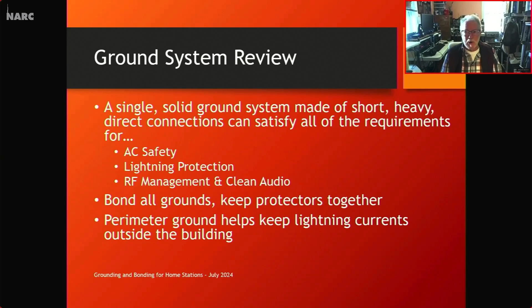You want to make sure you bond all these grounds and your protectors together so they fire at the same time, so everything goes up and down together and you don't get individual destructive transients. When you use a perimeter ground system, it helps keep lightning currents outside the building and helps the lightning get to earth—that's what it wants.